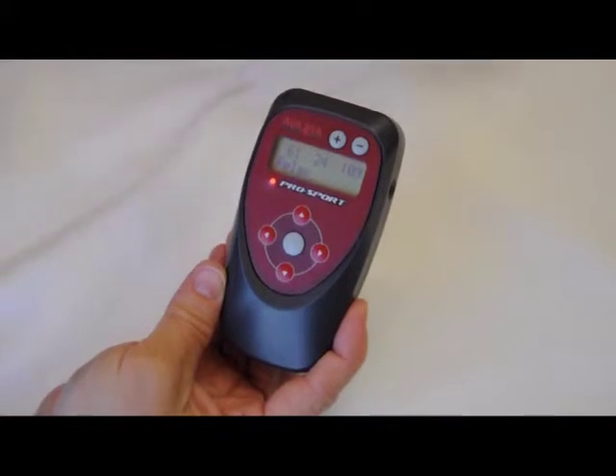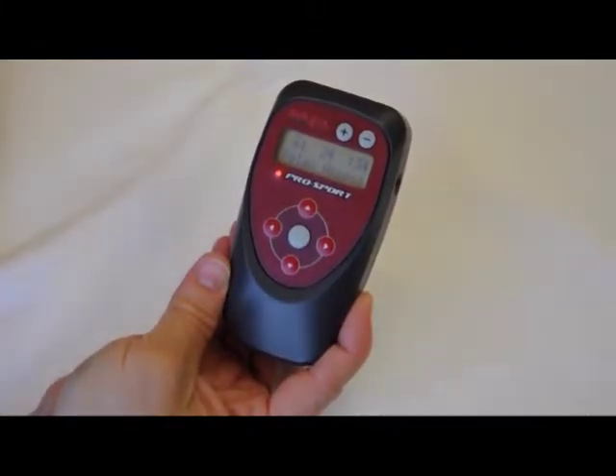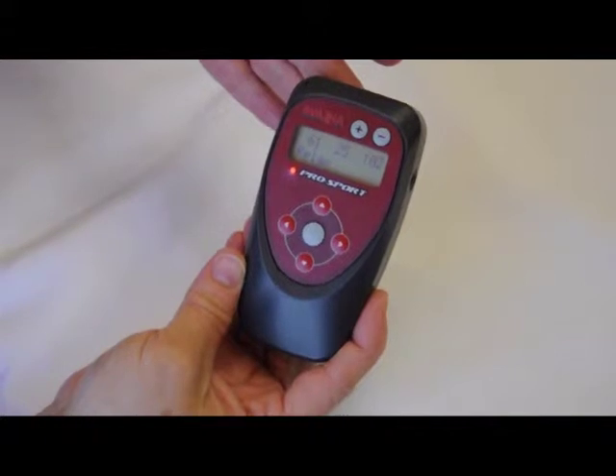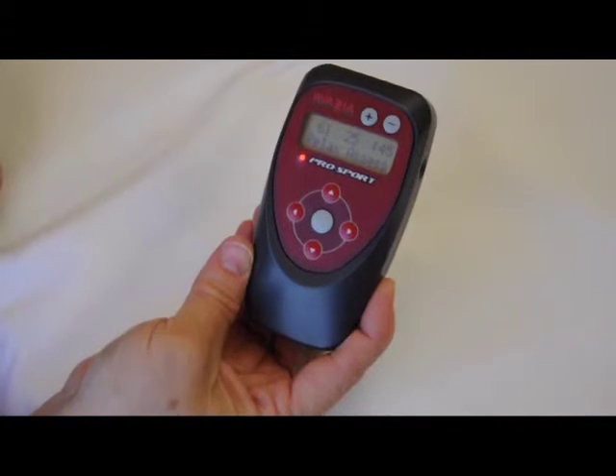When we remove from the tissue, the timer reverts back to the total amount of time in that mode. When we put it back on the tissue, the timer goes to the treatment time, and when we remove it, it reverts back to the time in that mode.